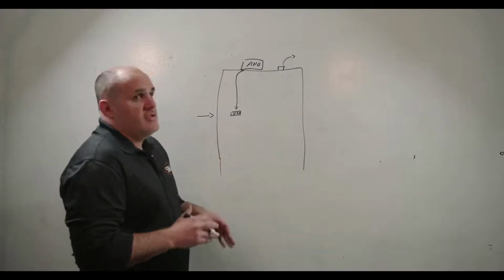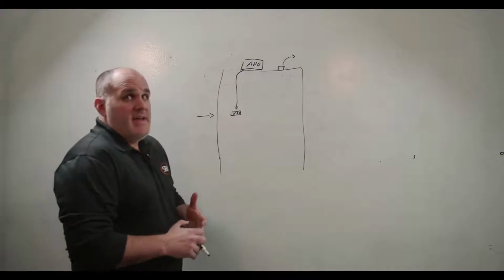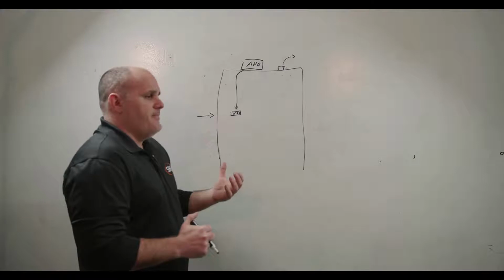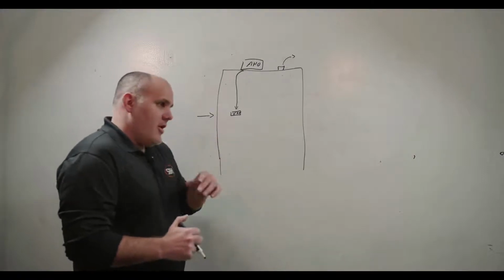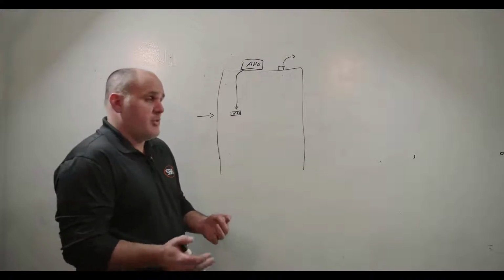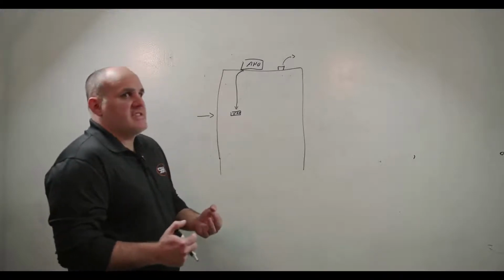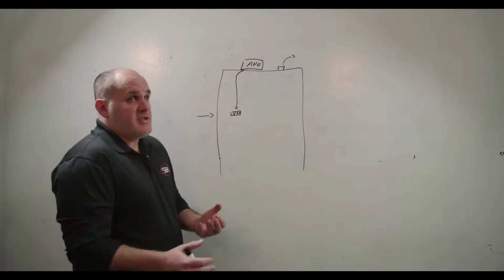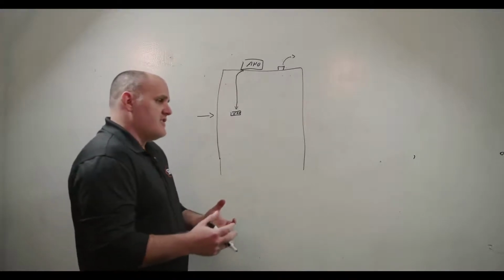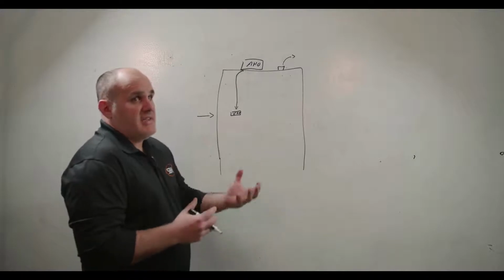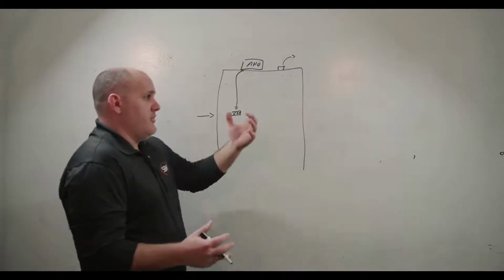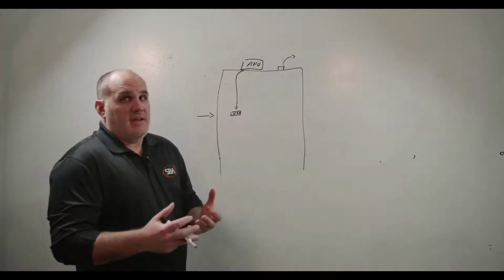Now, we can also do what is called fan tracking. And this is something that you'll see sometimes where you have a VSD and it's got a 60% signal on the supply, and then you do a 60% signal on the return/relief. And the theory is that the relief/return fan is smaller, and thus with fan curves, you are going to get a positive scenario because you're going to be relieving less volume than you're supplying. So that's kind of the scenario.